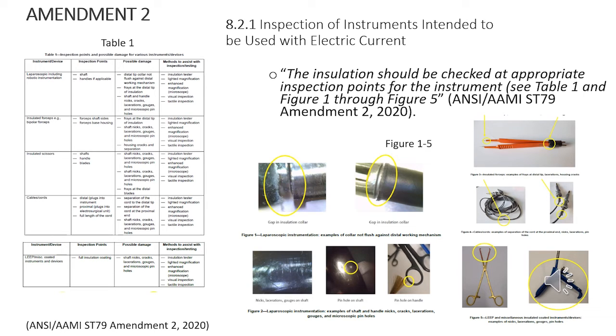Possible damage can range from frays at the distal tip, or at the proximal end separations, shaft nicks, and cracks. The methods to assist with inspecting and testing can vary based on the instrument itself. Some of the items listed under this section are an insulation tester, lighted magnification, enhanced magnification microscope, visual inspection, and tactile inspection, which would be using your hands to feel if there's any damage on that shaft or insulated instrument. In figures 1 through 5, this is the first time AAMI actually came out with pictures in color. And what's really nice is that these pictures, figures 1 through 5, match Table 1 of different things that could happen to the insulated device in regards to damage.